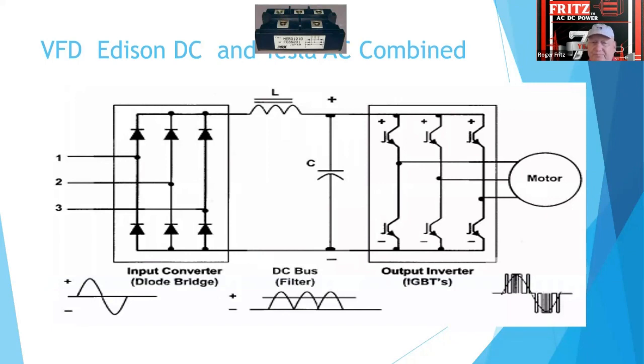And so this is what they call a bridge diode. Really what it does is it takes the three-phase power, which is your original sine wave coming off the generators, and they put what they call a link choke in here, and that's just to slow down current flow to the capacitors and to the transistors so that it doesn't surge, because surging ends up causing a lot of factors, especially on the old GTRs, which were gated transistors. Now they went to IGBTs, which are isolated gate type transistors. And they've also got the switching up a lot higher.